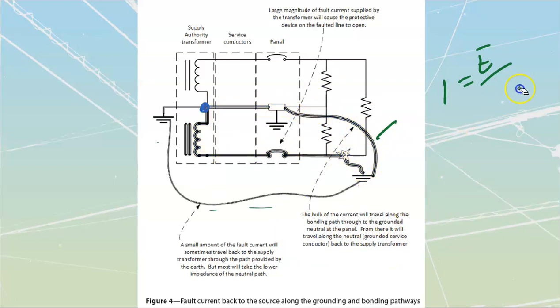We are supposed to make sure that our bonding path is low impedance. Inside of BC here, we're supposed to make sure that whatever our bonding path resistance is, it should be such that it's going to develop 5 times the protection current. So if I've got a 15 amp circuit, I need a bonding circuit for a 15 amp that is low enough impedance that I'm going to get 5 times that value. You just take 15 times 5, that gets you to 75, so I need to have 75 amps flow during the fault.